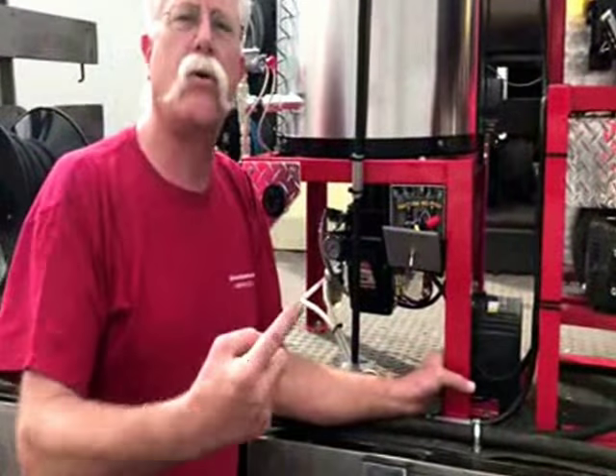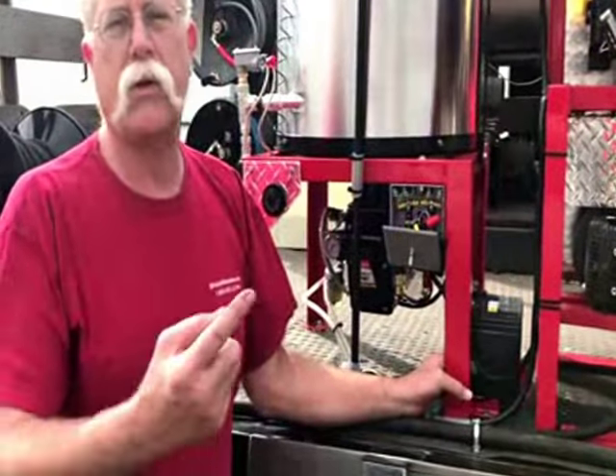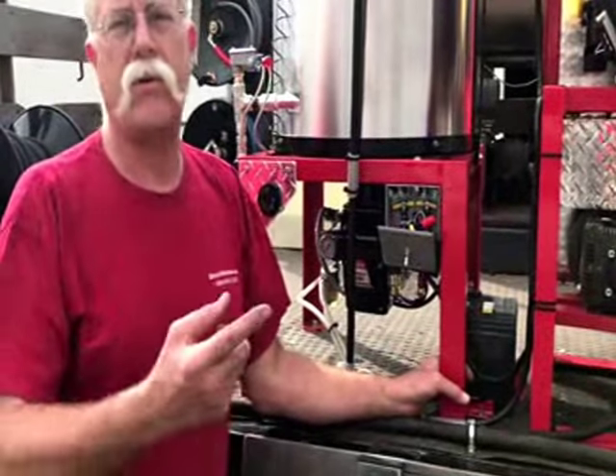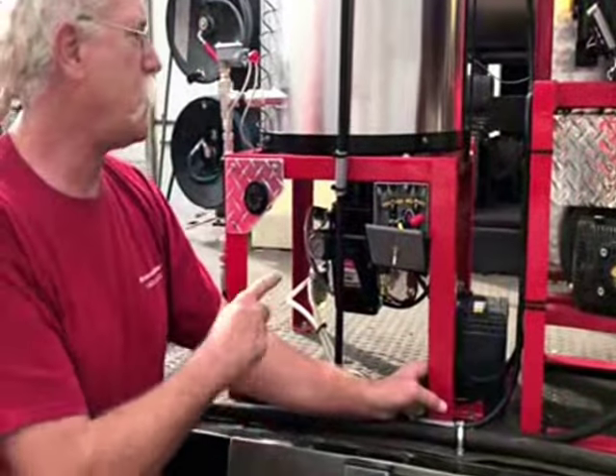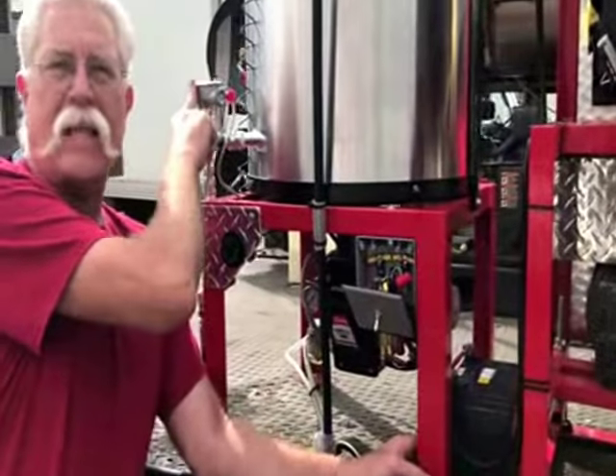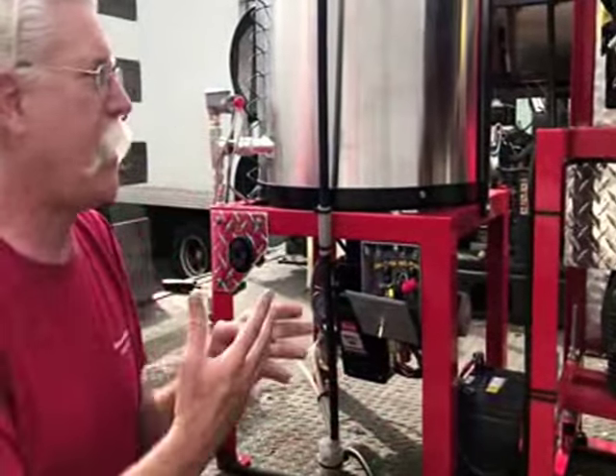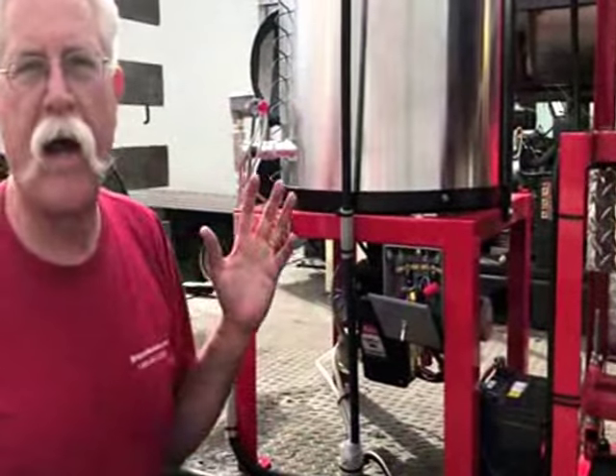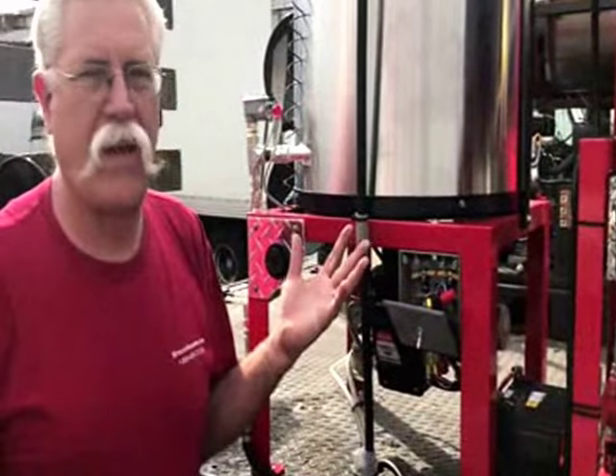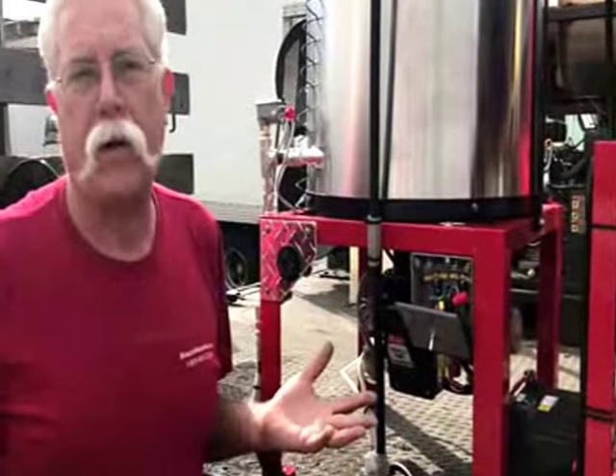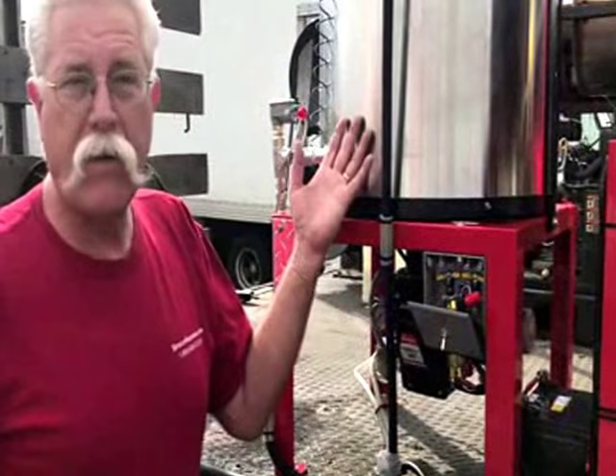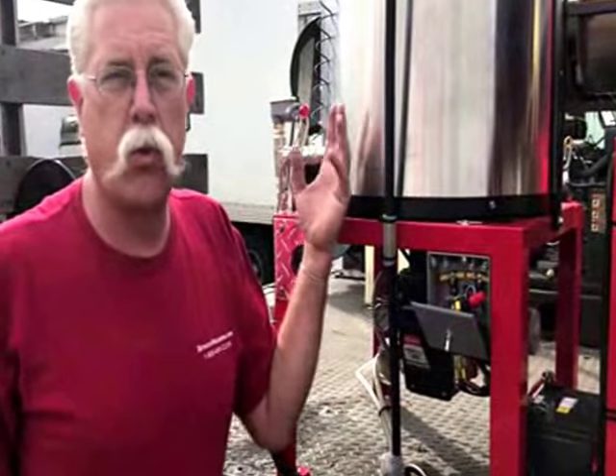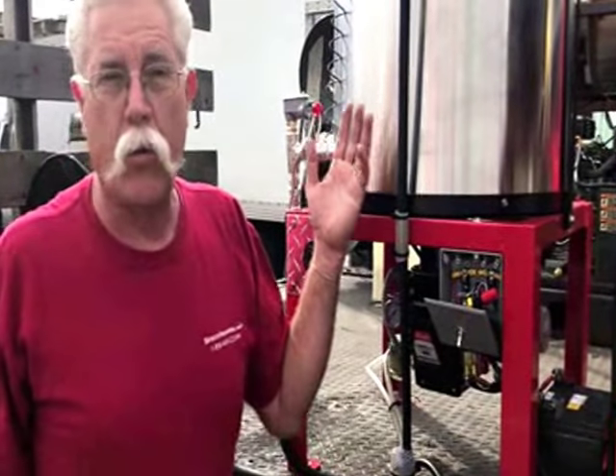It's because of the way we do the wiring, the controls, and the safety devices. Nobody else uses a redundant temperature control on the inlet of the heater so it can never get super hot from no water flowing and the heater stuck on. They don't blow up like other machines do. So the outcome is we've got machines out there that are 28 and 30 years old with the original heater coils. It just never had to blow up.